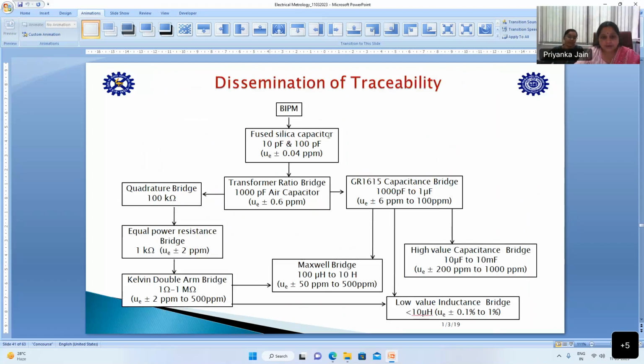We have fused silica reference capacitors, which are 10 pF and 100 pF values. They are traceable to BIPM. BIPM is defining our capacitance standard from the quantum Hall resistance standard through a chain of coaxial impedance bridges. Then we have a transformer ratio bridge, where we can derive a 1000 pF air capacitor. From this bridge, we are defining the capacitance range from 1 pF to 1 microfarad.